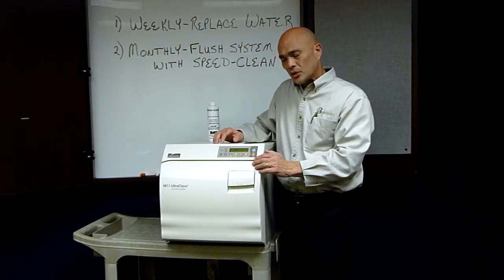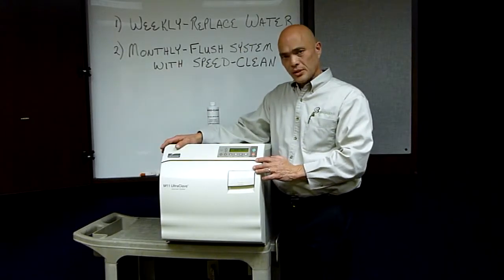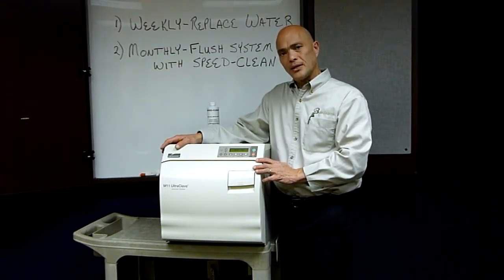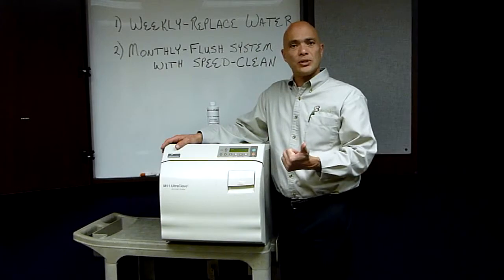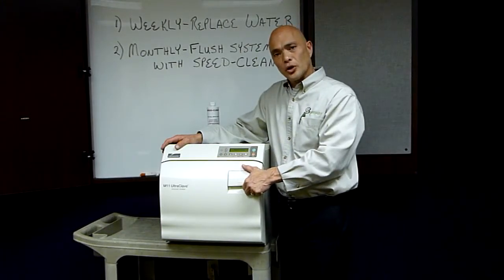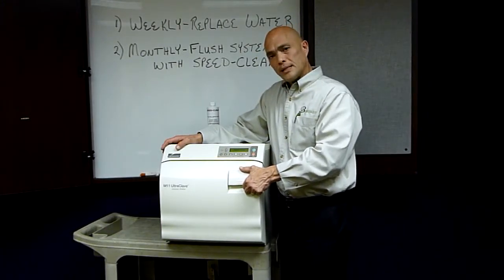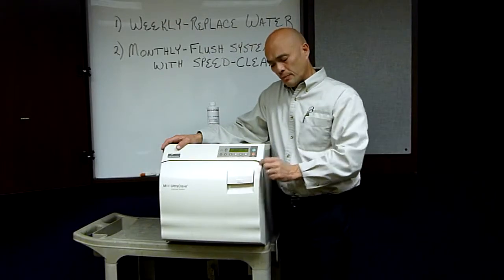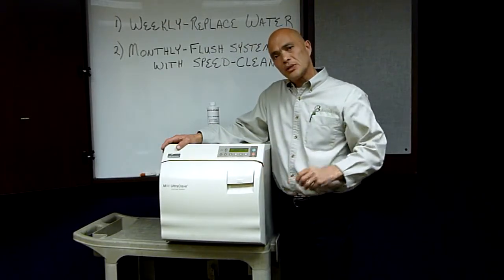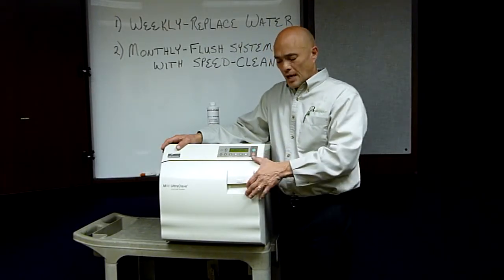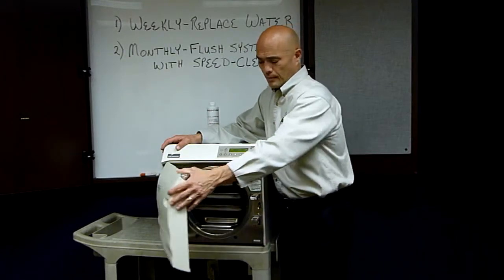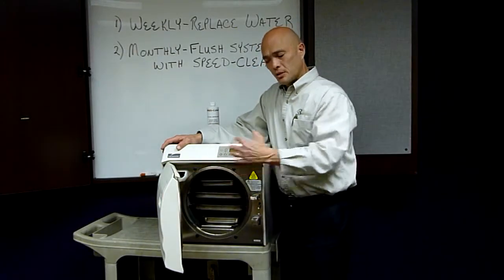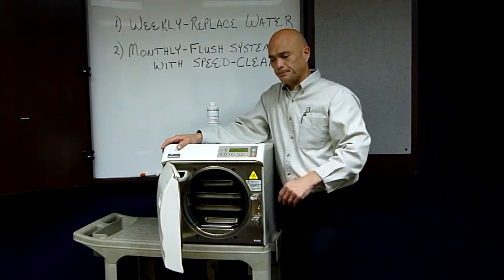At the end of that cycle time, you're going to hear a series of 5 beeps. That indicates 2 things: that the sterilization cycle is done and that the door is going to open. The door slowly raises, it pops open about a ½ inch, and it releases all the steam from the chamber. At this time you can open the door and have access to your instruments. Your drying cycle is still going on.